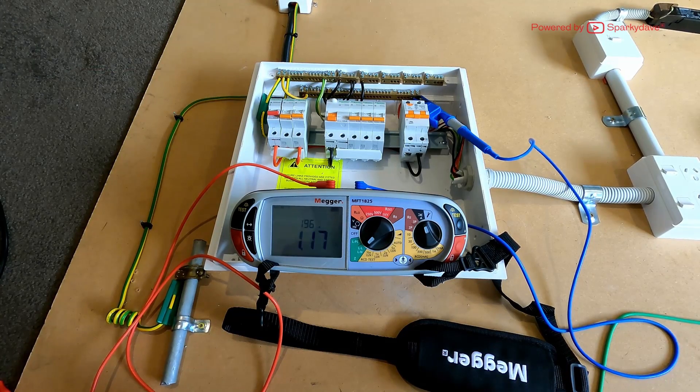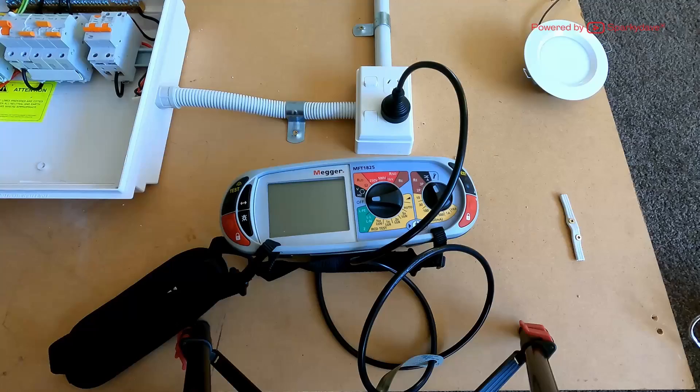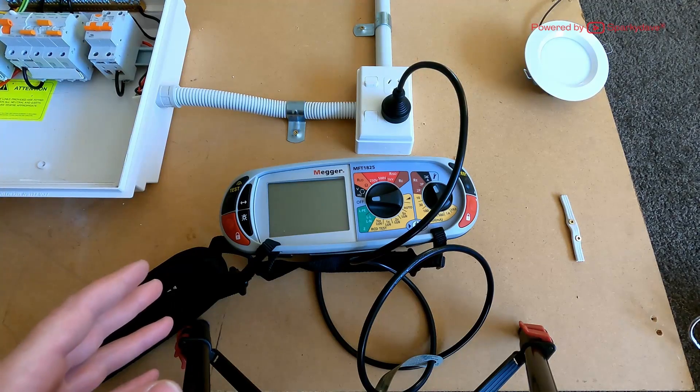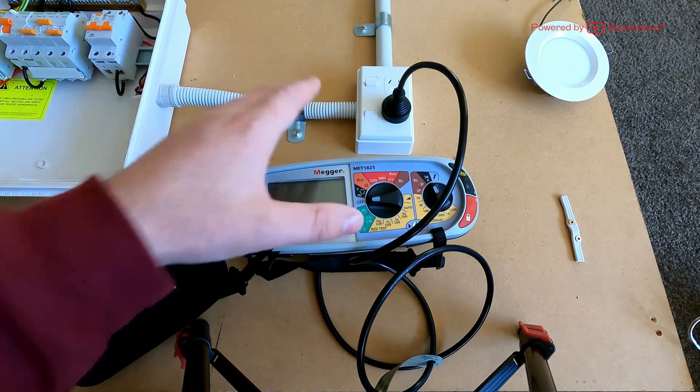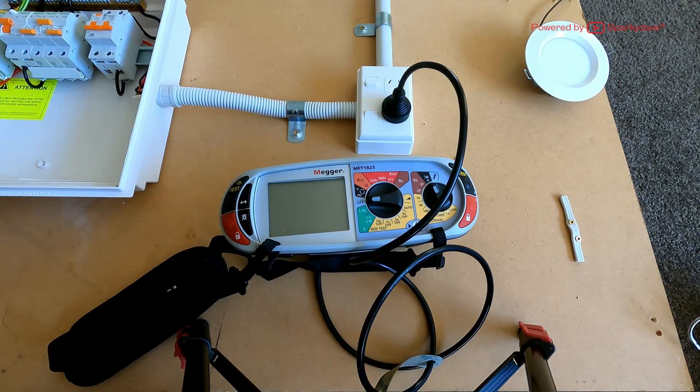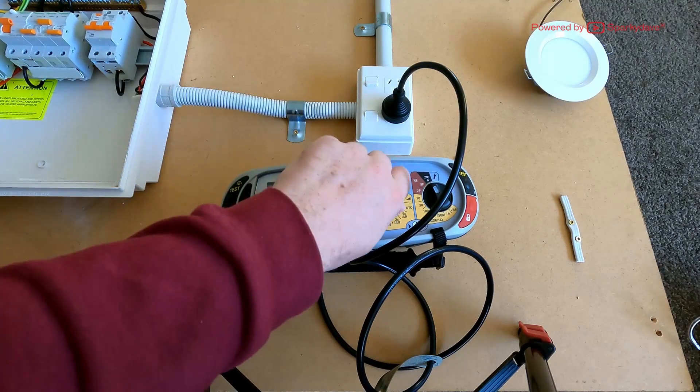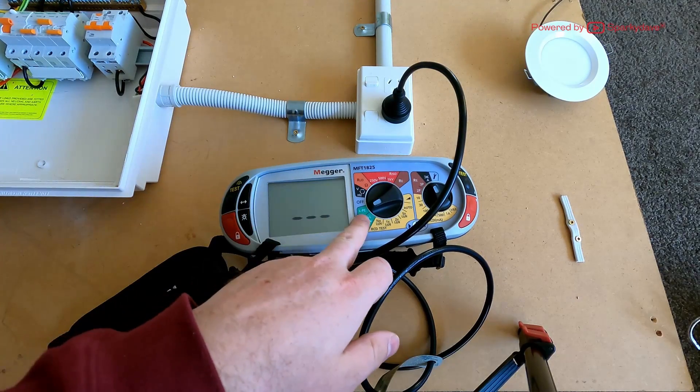Exactly the same reading. I don't think the reading is going to get any better than that. All right, so now we'll do our second test, and that's going to be from the furthest socket from the installation. Obviously this one's pretty close by. First of all, we'll do our line to earth test.